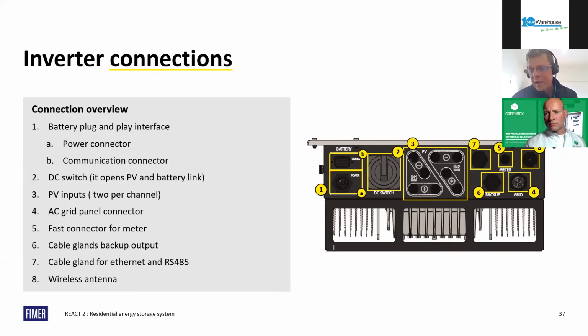Some of the connections underneath the inverter, obviously the number 3 in the middle is your DC input with 2 channels. Your DC switch is compliant to AS5033, and the battery connections, which makes this one of the easiest battery solutions to install. The battery module comes with 2 cables. It's just plug and play. And on the other side, you have the AC backup port to connect any essential power, as well as any metering. Even the connection of an energy meter is through a plug as well.